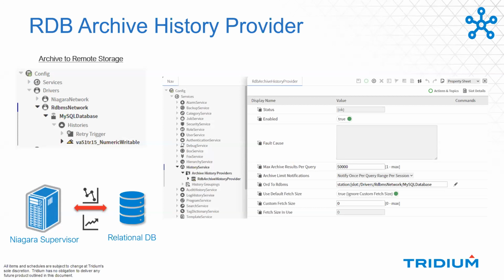And we'll have a demo shortly, so you can see how the workflow works. Once you've added this new RDB archive history provider to your history service, you've now told Niagara where it can find additional records for a given history database. And so if I were to now pull up the table, I'm not just looking at the 5 results that are sitting in the Niagara history space. I'm looking at the complete data set, 5 records at the local and the remaining data set that's found in the RDB.